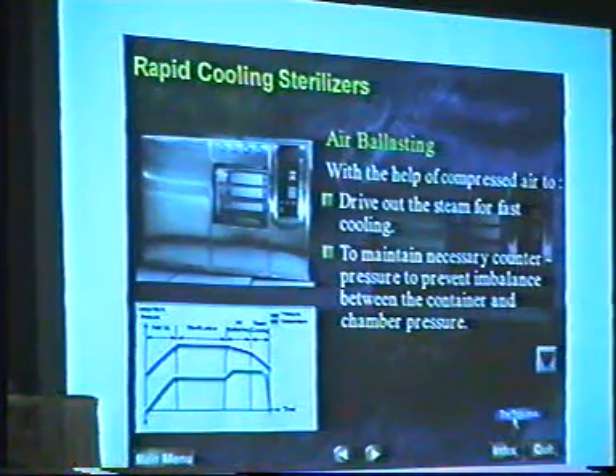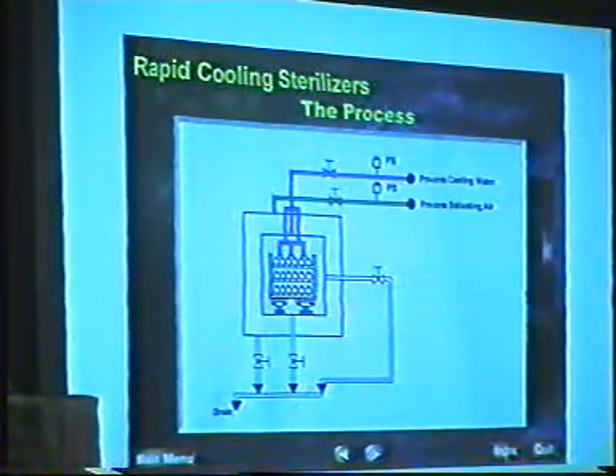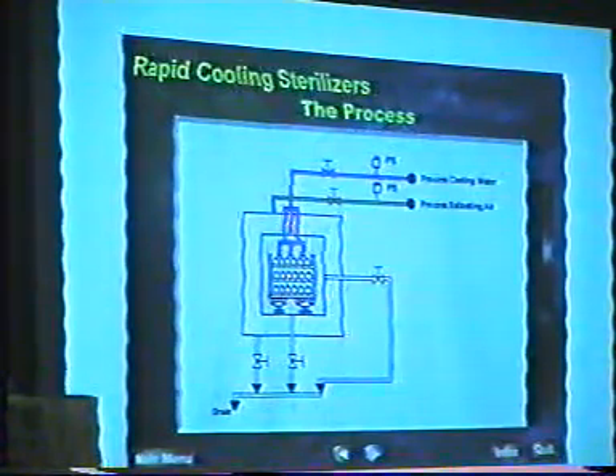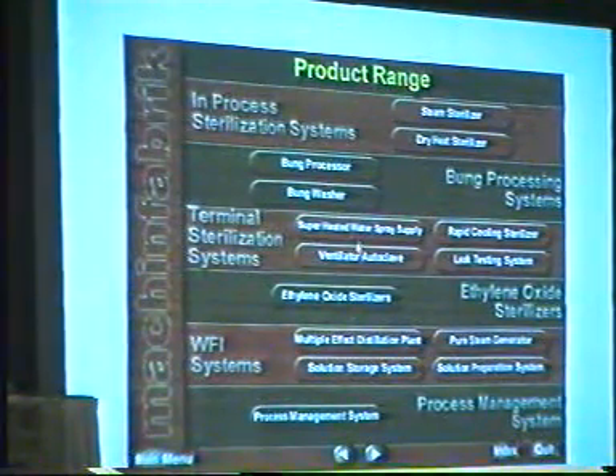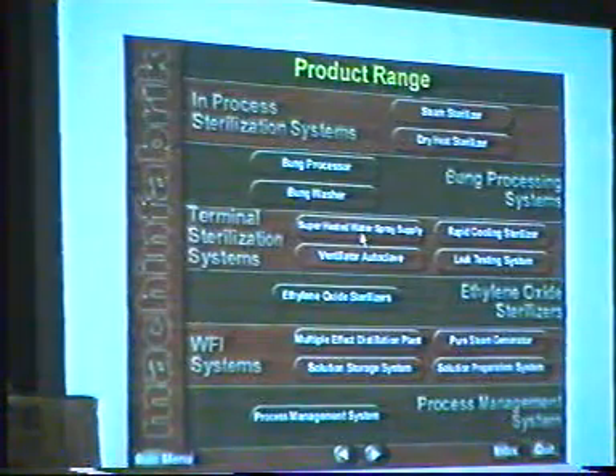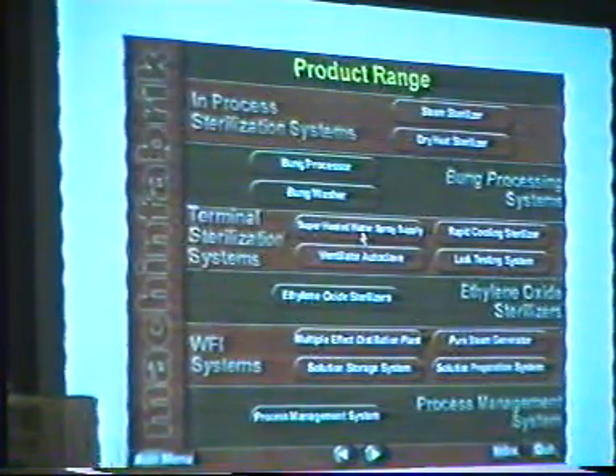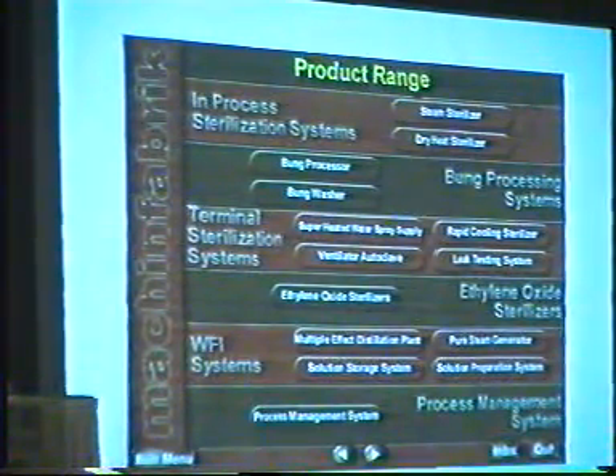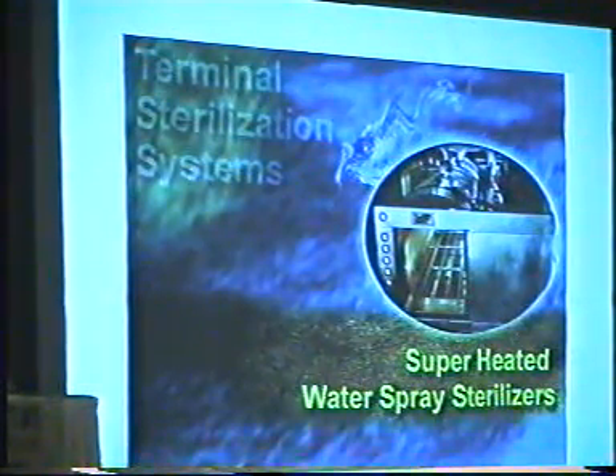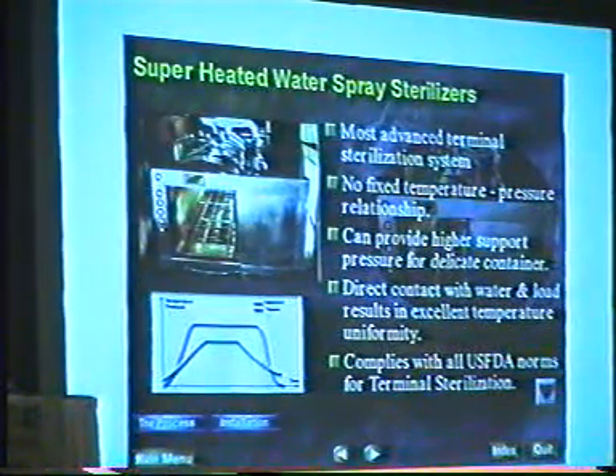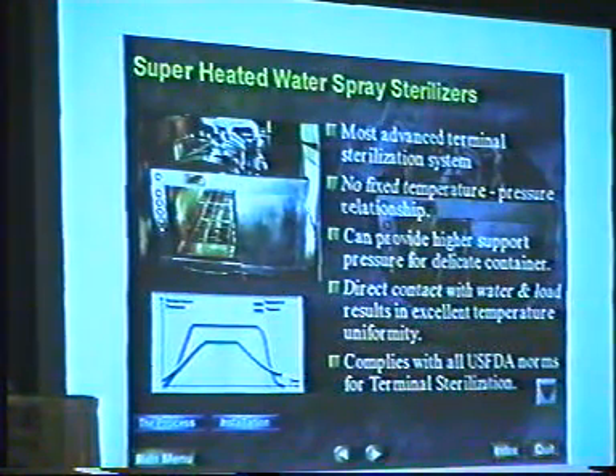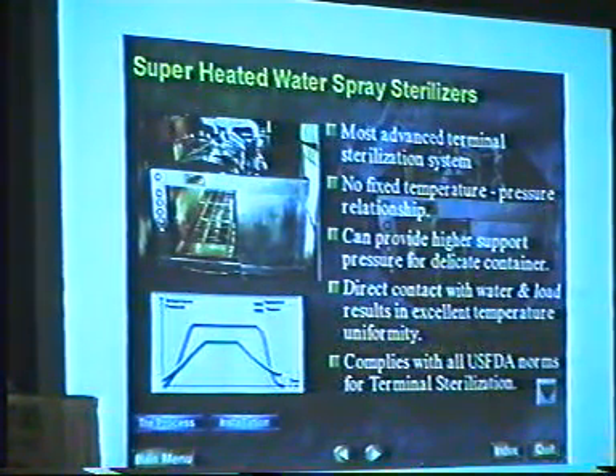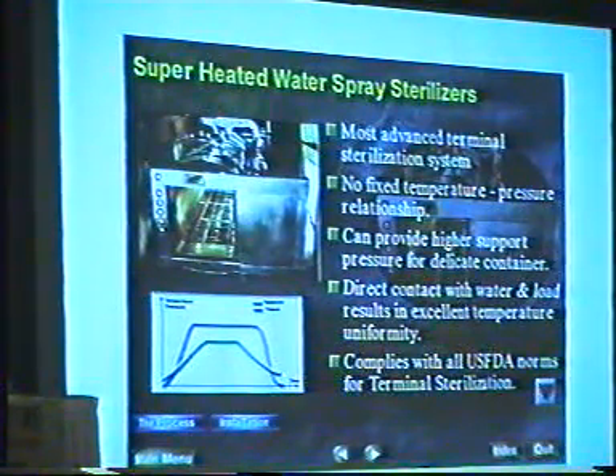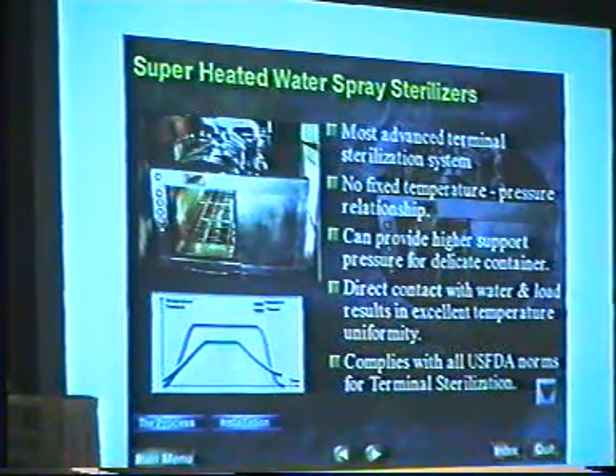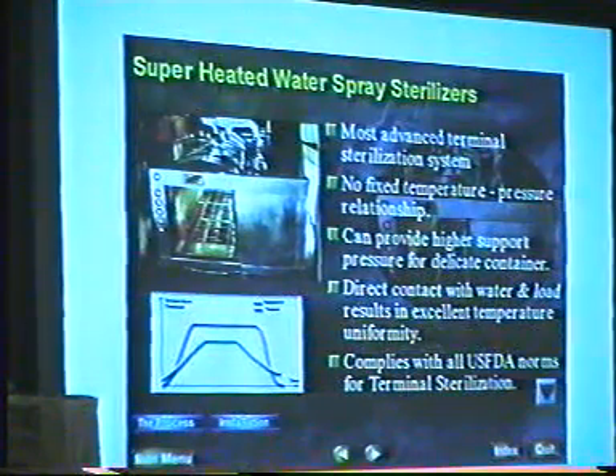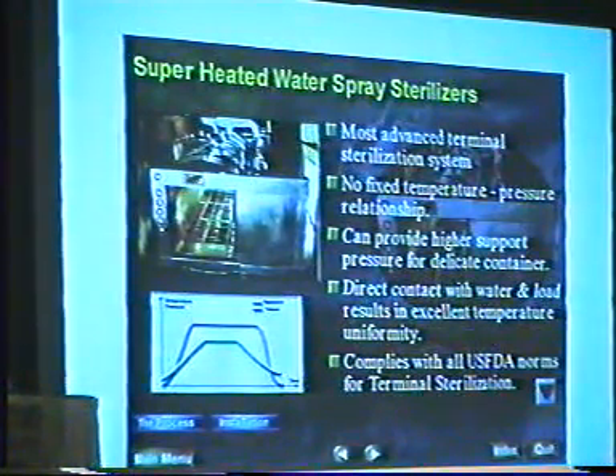This now brings us to two new additions to the terminal sterilization processes. One is the superheated water spray sterilization process, and the second is the isothermal sterilization process. Both these processes were essentially developed because the container changed from glass to plastic. When you change container from glass to plastic, the glass will withstand certain pressure and temperature shocks. The plastic will not. Hence, it was impossible for certain kinds of containers to be processed in conventional sterilizers. That is how these systems were developed.